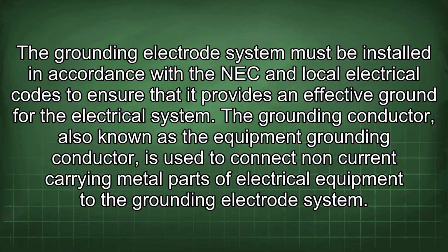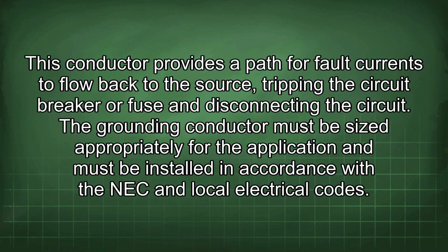The grounding conductor, also known as the equipment grounding conductor, is used to connect non-current carrying metal parts of electrical equipment to the grounding electrode system. This conductor provides a path for fault currents to flow back to the source, tripping the circuit breaker or fuse and disconnecting the circuit. The grounding conductor must be sized appropriately for the application and must be installed in accordance with the NEC and local electrical codes.